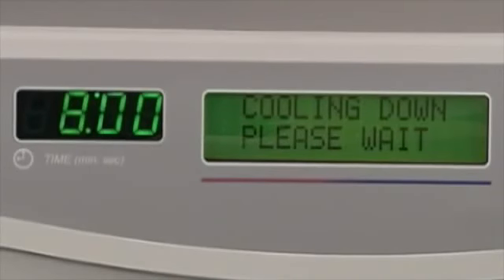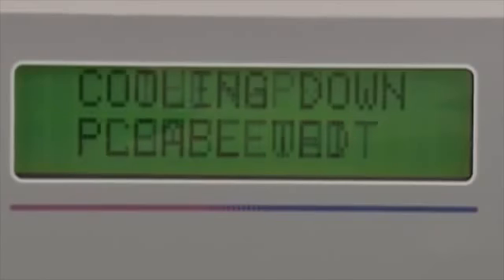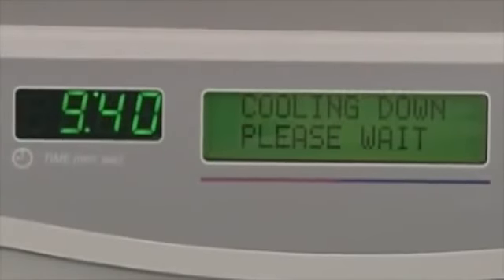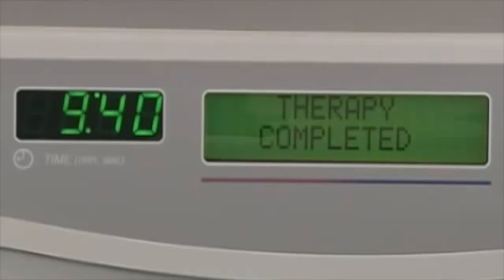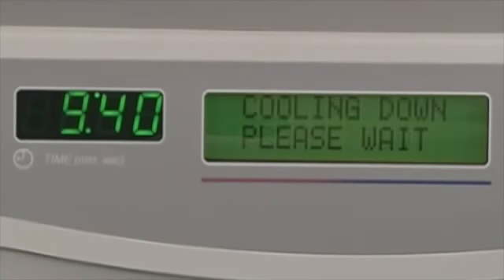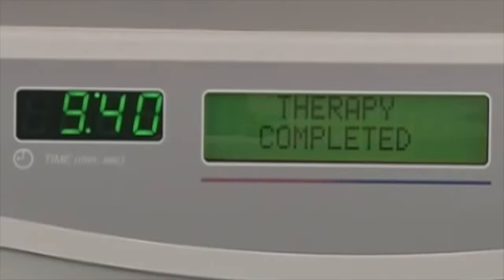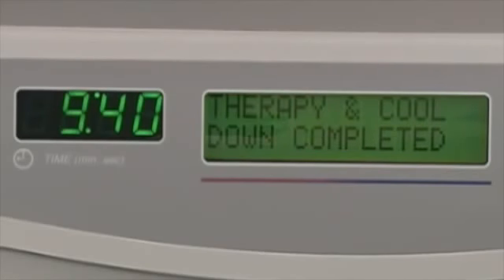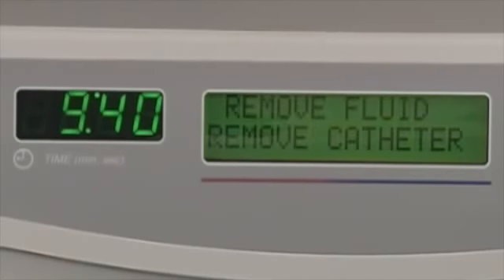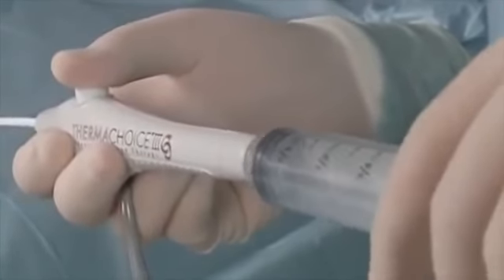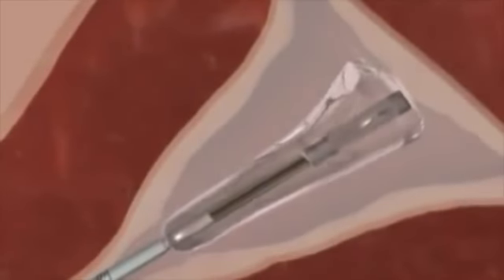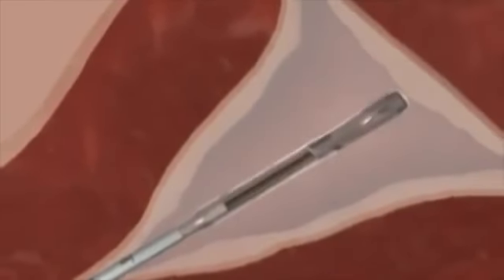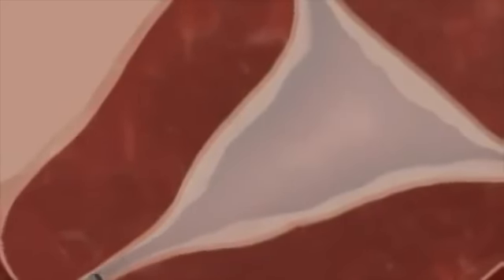Upon completion of the therapy cycle, the heater is automatically deactivated and the fluid is allowed to cool for 30 seconds. You'll notice that the time display now indicates the total therapy time of 8 minutes, plus the original preheat time. Once the fluid is cooled, the message display will read "Therapy and cool down completed," and then "Remove fluid, remove catheter." Deflate the balloon by depressing the trumpet valve and removing all the fluid. Then withdraw the catheter from the uterus.